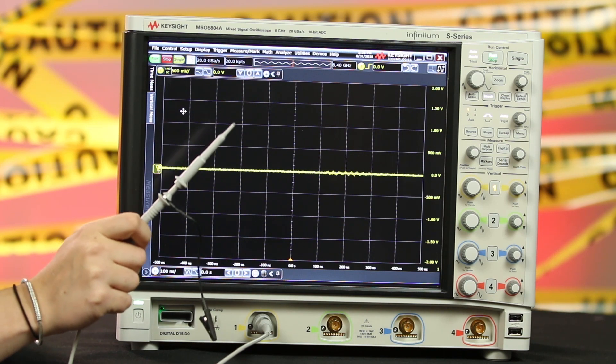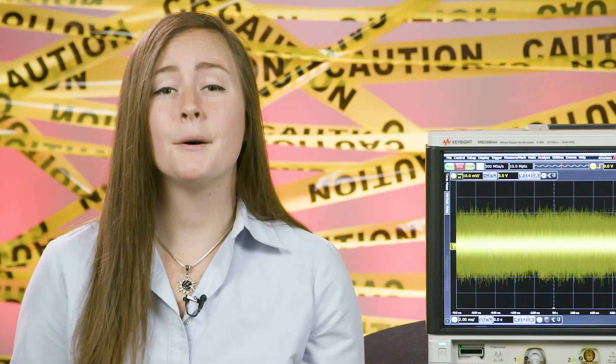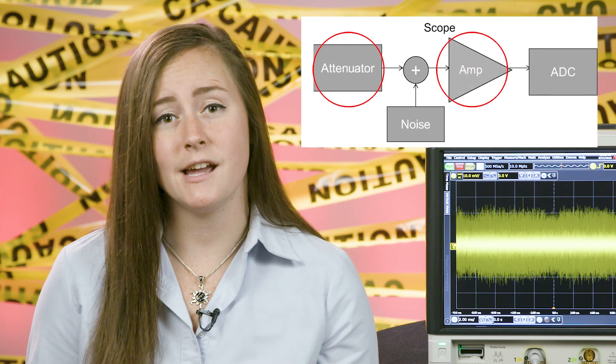So first things first, what is this noise and where is it coming from? Well, some of it's actually coming from the oscilloscope and probe that you need to use to measure your signal. You'll see this on every scope from every vendor. It's unavoidable and it's called random noise. It comes from the technology that's used in the scope's front end, the attenuator and the amplifier.